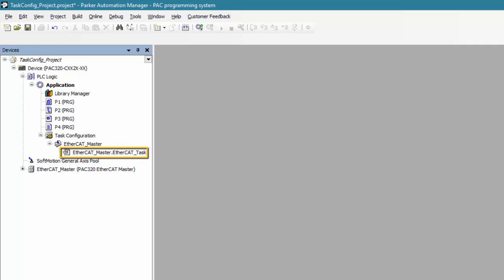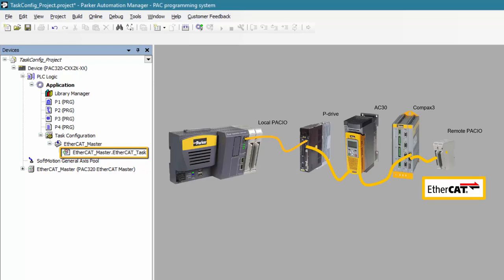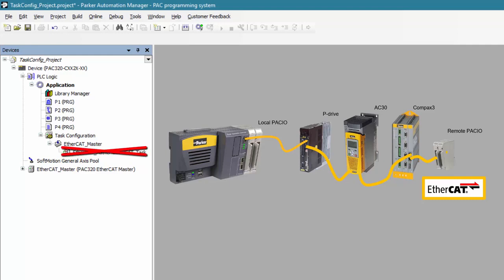The EtherCAT_master.EtherCAT_task is a special object that represents the actual EtherCAT read write bus cycle of the PAC controller. If this object is renamed or deleted, your EtherCAT bus will fail to run.